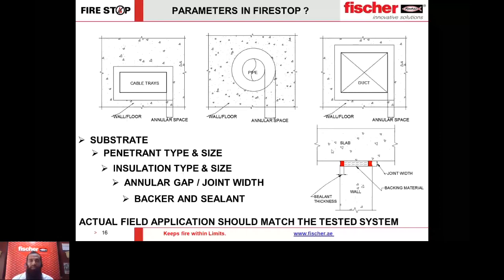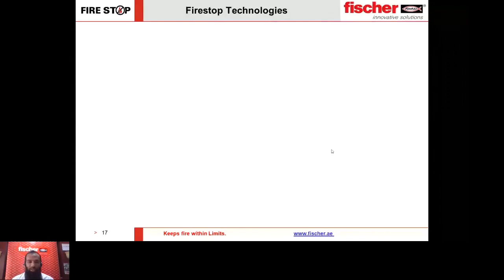All of these parameters are always mentioned in the solution provided, and when I talk about solution it is either a UL listed system or a BS listed system. You need to make sure that the actual field application matches exactly with these parameters within the solution, otherwise the fire rating will not be reinstated and it would remain zero.